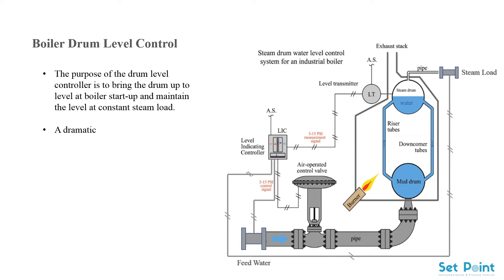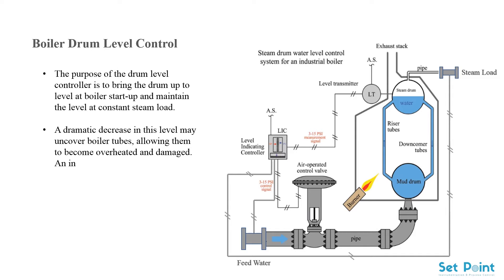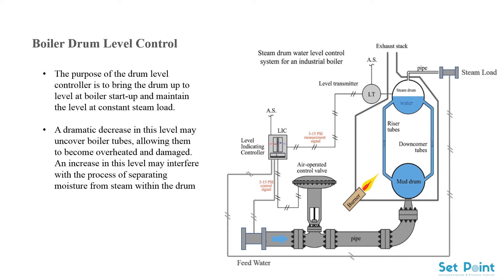A dramatic decrease in this level may uncover boiler tubes, allowing them to become overheated and damaged. An increase in this level may interfere with the process of separating moisture from steam within the drum, thus reducing boiler efficiency and carrying moisture into the process or turbine.